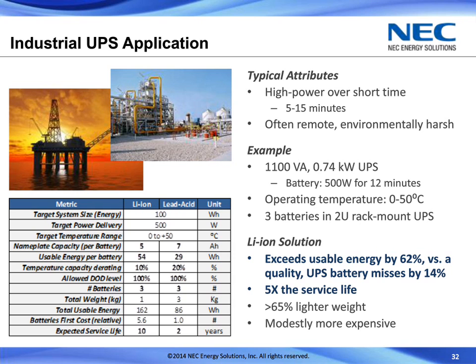0 to 50 degrees C, and rather than scaling the lead, oversizing to meet the power and energy requirements, for this example we're sticking with the 3 batteries in this form factor of the 2U rack mount UPS. So you can see the usable energy for the lithium, 162 watt hour versus 86 for the lead. And again, partly because we didn't oversize the lead for this example.